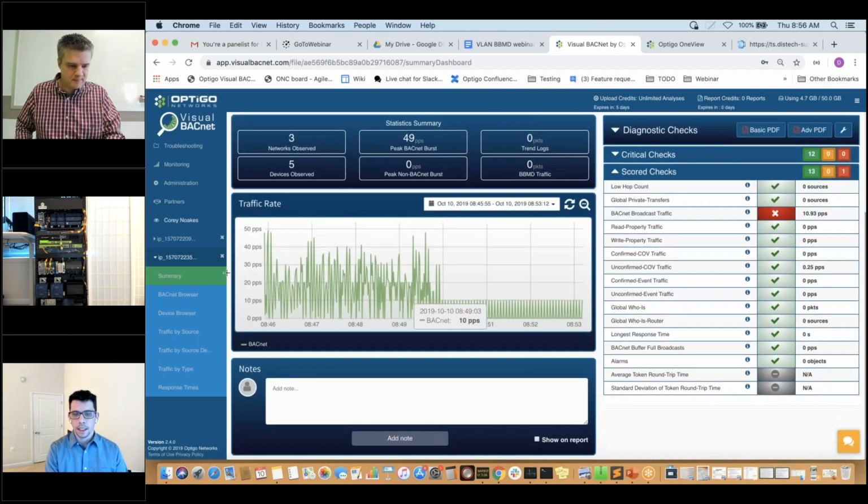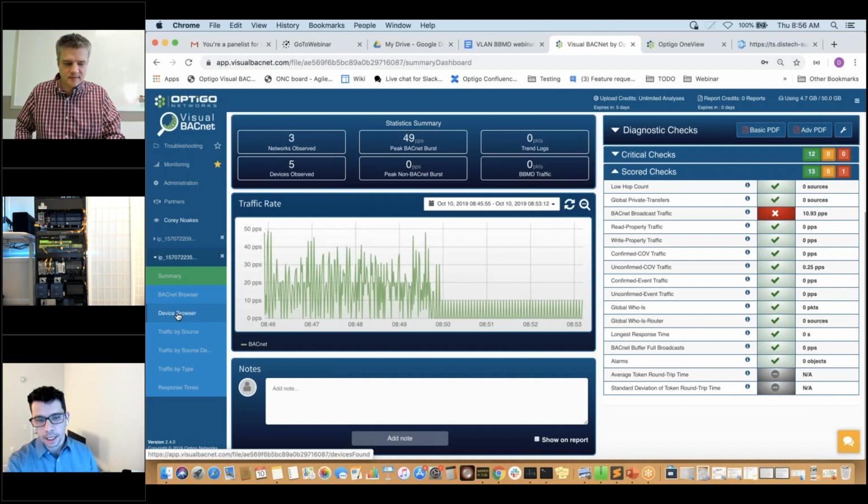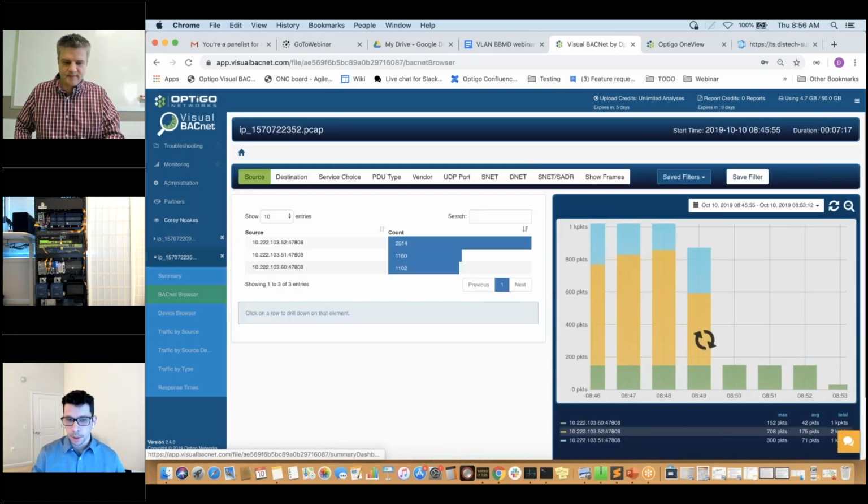And it's worth noting in this chart, you see the traffic remaining is just the zone controllers. And it stands to reason. You're going to have a lot of traffic if you have air handlers or larger mechanical systems, or you have a chiller plant or a boiler plant. There's probably going to be a lot of communication going back between the supervisor and other controllers. And so those networks tend to be a little busier.